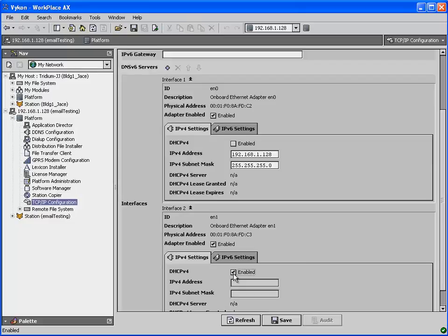There is a caveat, however, that only one of the network interface ports on the JACE can have DHCP enabled on it at a time. So just keep that in mind. Only one port at a time. The other two can be set manually. You could use all three network ports simultaneously on a JACE 7, for example, the Wi-Fi, and both the primary and secondary network ports, but only one port can have DHCP enabled at a time.